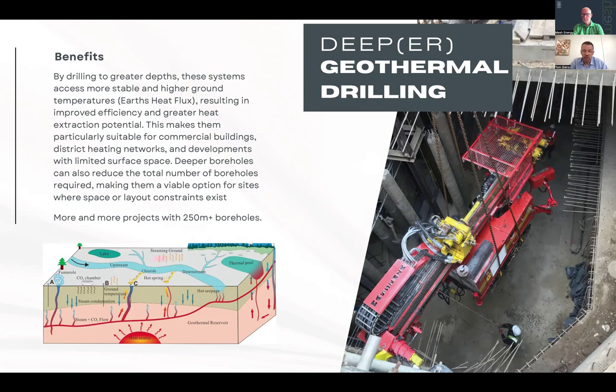So in larger projects, commercial systems, this is being considered quite a lot to reduce the number of boreholes or improve the efficiency of the boreholes. The boreholes are calculated or designed to a slightly higher depth. We're talking 250, 300 meters or even more. Some of our drilling rigs can drill to 300 meters. That's not what we do very often, but we've done 250 meter boreholes. But yeah, it comes with a bit more risk of the boreholes collapsing. Again, it might be slightly more expensive, but in the long run, that will provide better performance of the system. And again, you can reduce the borehole depth.